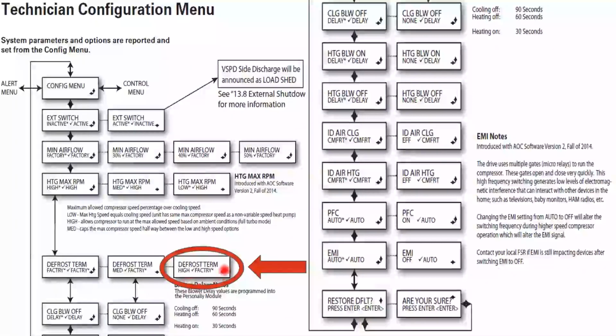So when we set it to defrost termination high, it's going to defrost a little bit longer until that coil temperature sensor reaches 67, and in some cases, up to 70. So what that means is that defrost is going to run just a little while longer, and it's going to eliminate all that ice. So if we do have a defrost ice buildup or frosting issue, let's set that defrost termination from factory to high. So you're going to cycle over 3 and then press the center button, and it's going to save it. You'll see the little check mark near high.